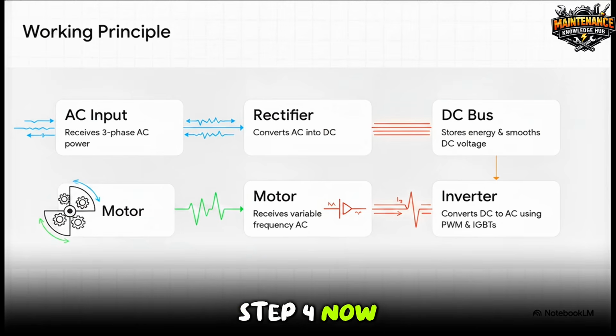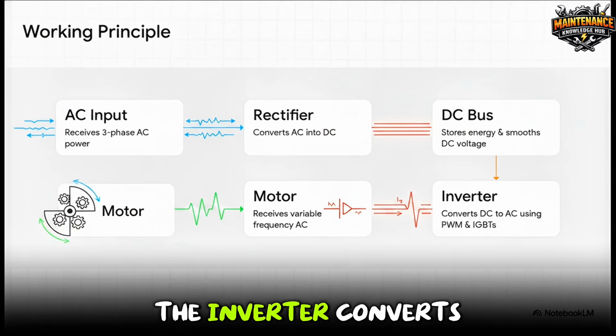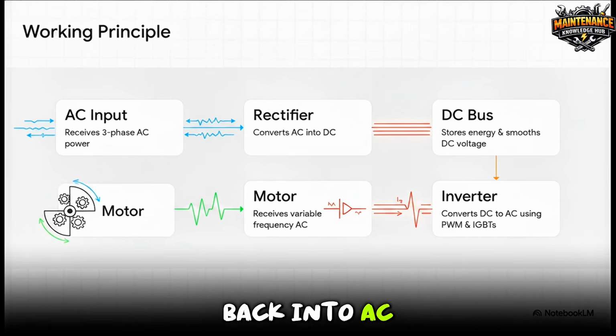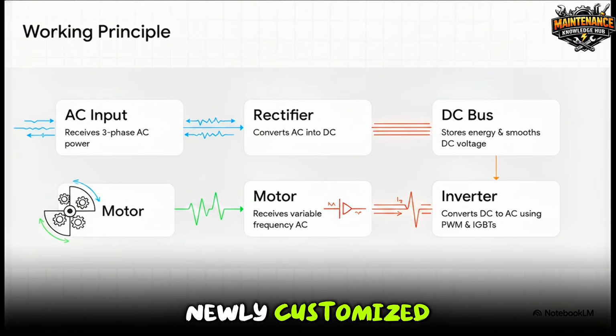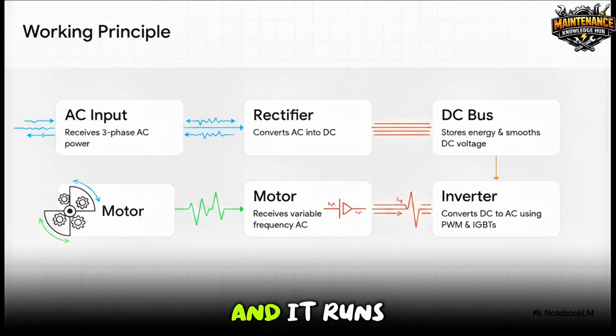Step 4, now this is where the magic happens. The inverter converts that smooth DC back into AC. It does this using IGBTs, insulated gate bipolar transistors, which are literally switching on and off thousands of times per second using a technique called pulse width modulation, or PWM. And finally, step 5, the motor receives this newly customized variable frequency AC power, and it runs at the exact speed dictated by the drive.